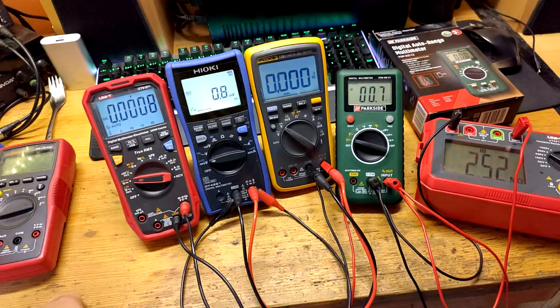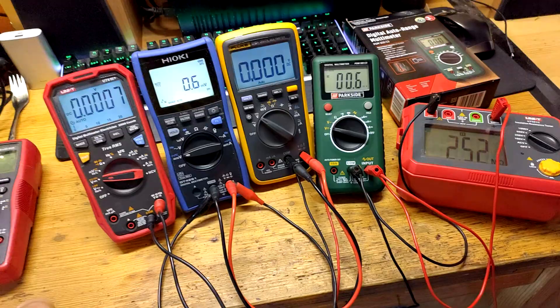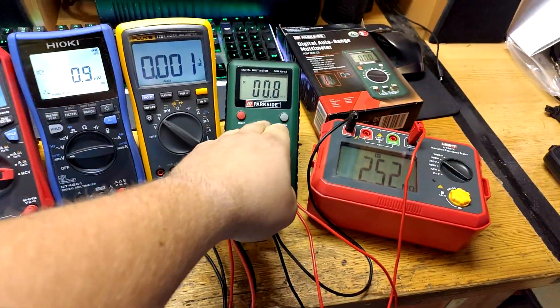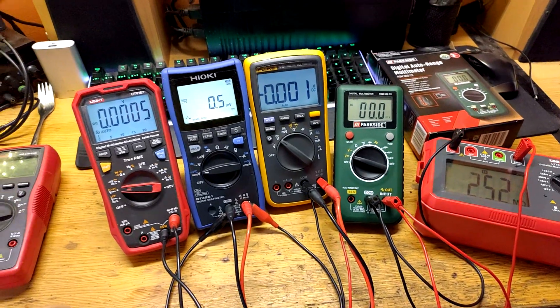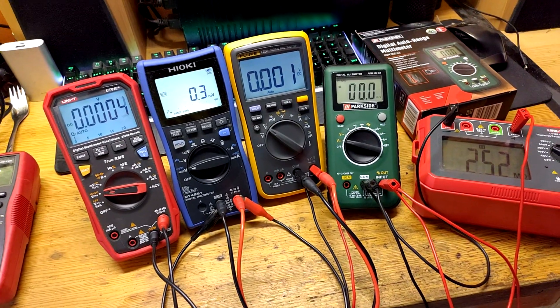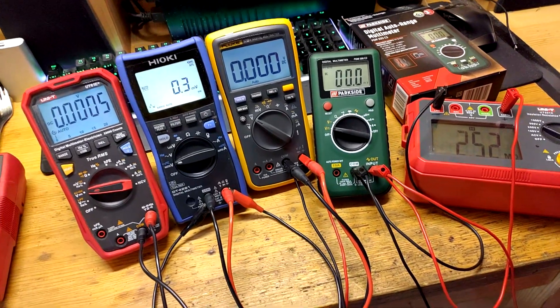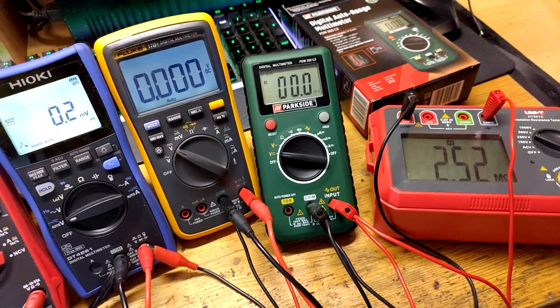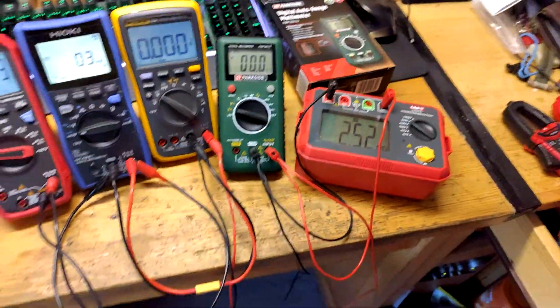Hello people, there is this one thing I figured out. I was preparing my review for this Fluke multimeter and for this Parkside multimeter, and I was just at the category of overvoltage warning when I discovered that the Parkside multimeter shows zero volts even if you apply high voltage to it. Let's see.